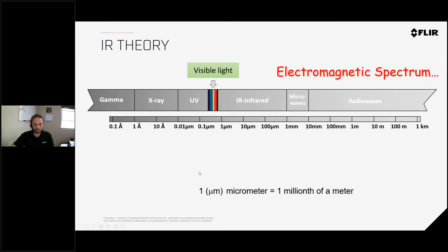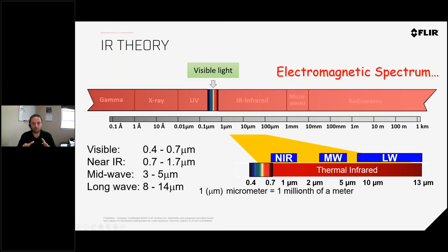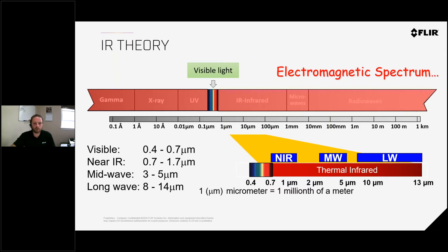One micrometer is one millionth of a meter — very, very tiny. When we look at infrared, it's just past the visible spectrum at 0.4 to 0.7 micrometers. Then you have near IR at 0.7 to 1.7, mid-wave at 3 to 5, and long-wave at 8 to 14 micrometers. Most of the cameras we're going to talk about today are long-wave infrared in that 8 to 14 micrometer range, which are the most common handheld thermal imaging cameras.